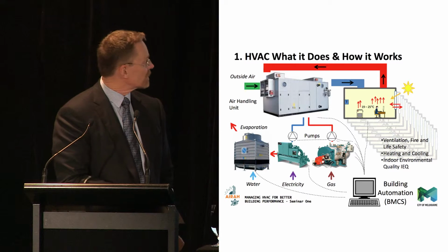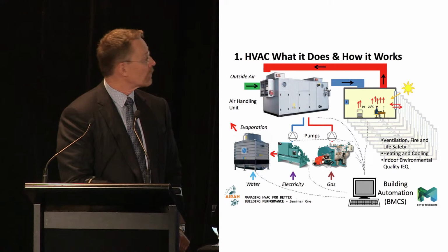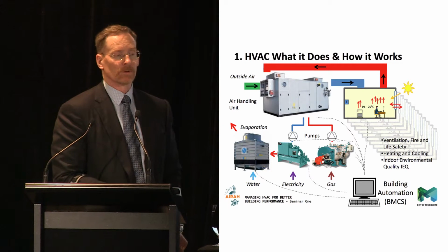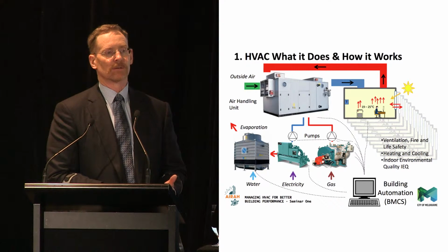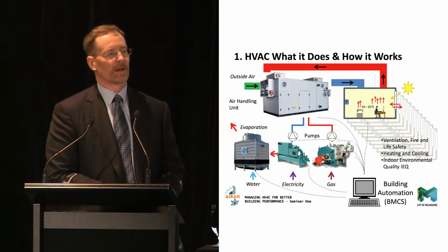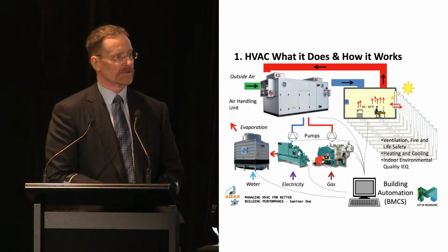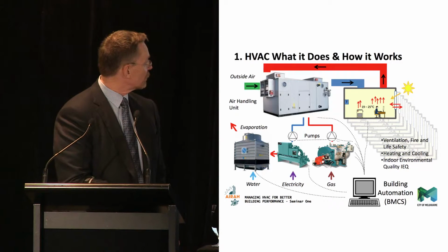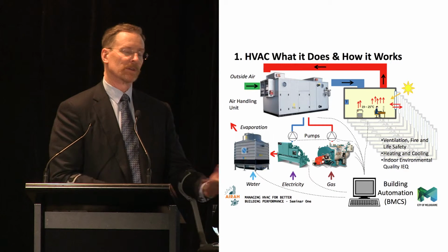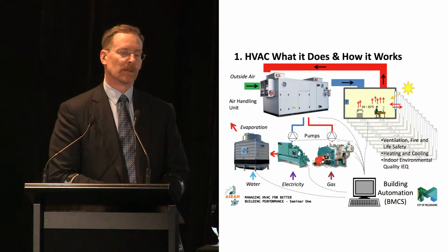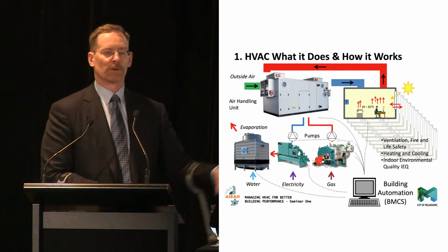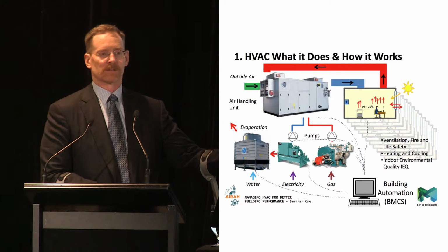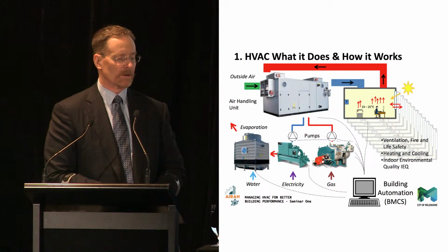So what I'm saying is the chiller, once it takes the heat out of the water, needs to put that heat somewhere. And typically in a building, that heat is exported to a cooling tower, and we use evaporation to cool that water down. And then that water is cycled back to the chiller at a cooler temperature. So that's why you've got cooling towers in the building. They're effectively exporting the heat or the energy to the atmosphere using evaporation, if you like. No different to putting a wet, sweaty arm out of the window when you're driving along in your car. Your arm feels cool. That's what evaporation does. It takes the heat away.